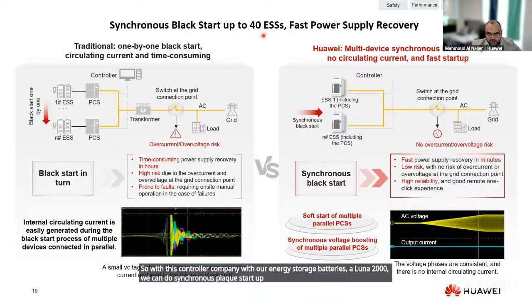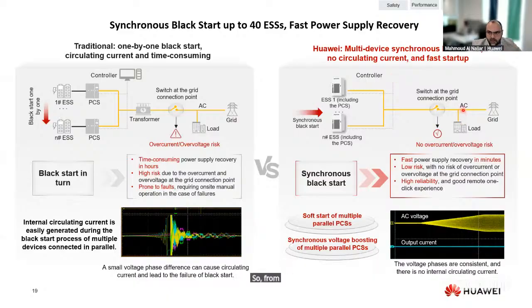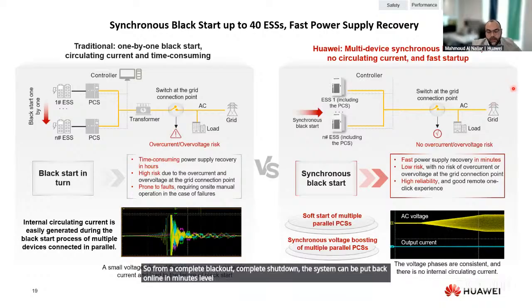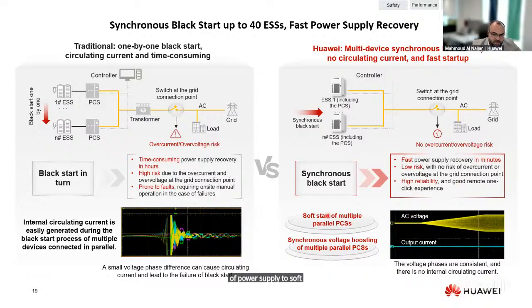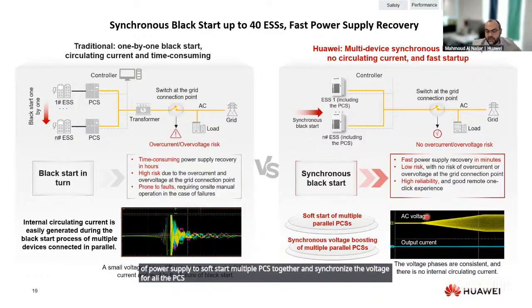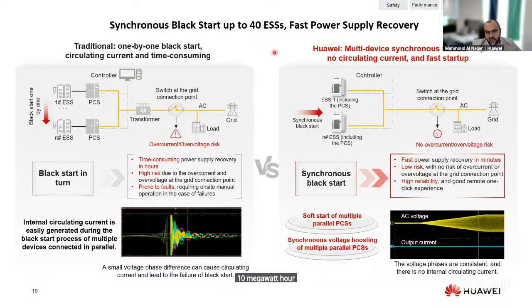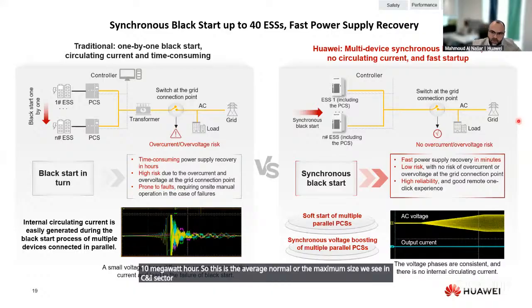black start up to 40 cabinets together to provide fast and easy supply recovery of the power. So from a complete blackout, complete shutdown, the system can be put back online at the minutes level, to soft start multiple PCS together and synchronize the voltage for all the PCSs to provide stable power operation of these batteries. 40 cabinets is roughly around 10 megawatt hour. So this is the average or maximum size we see in the C&I sector. Of course, if you have larger capacities, then we have other solutions with containers.